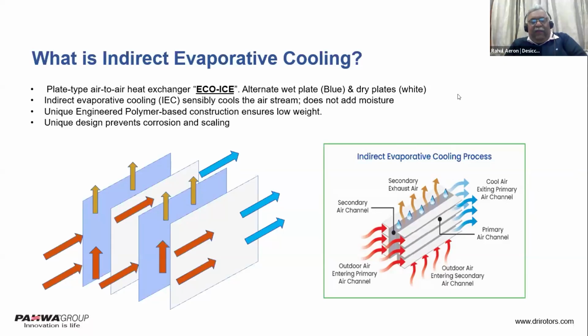This is called an indirect evaporative cooling system, because when I mentioned a direct evaporative cooling system, you tend to add some moisture or water vapor into the air. So when you add water vapor into the air, when it comes to your building, you always have a problem of what we call humidity control. So there we have a unique system design, or a heat exchanger design, wherein the heat exchanger will only reduce the temperature. It doesn't actually add moisture to the air stream. So these are called indirect evaporative cooling systems. Again, they work on water only.